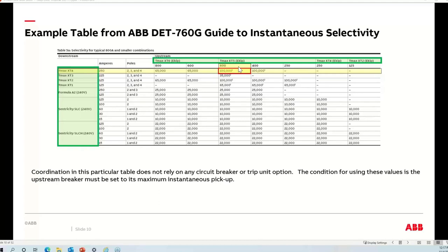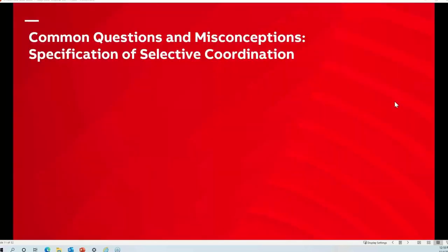As I mentioned, there are typically notes, assumptions, or requirements listed in the vendor's document — do be very careful to read those. For example, the upfront paragraph ahead of this table explains that if the trip unit has adjustability, the trip unit instantaneous pickup must be set at maximum for these values to be valid. So circuit breakers can coordinate, and using vendor coordination tables for the instantaneous region is a vital skill.